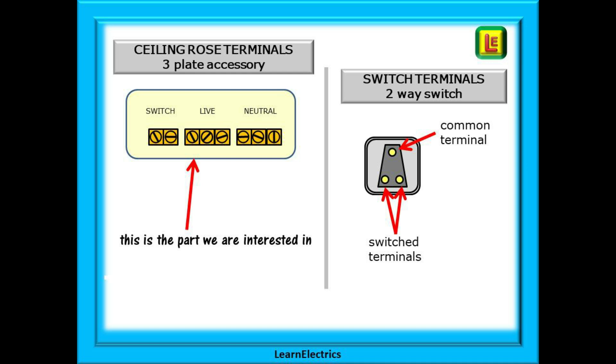Also shown here are the terminals for a two-way switch. One of the holes will very obviously be separate, a little further away from the other two. This is the common terminal and on some switches it may even be marked as COM for common. The other two holes are the switched contacts and only one of these is connected to the common at any one time depending on the switch position.